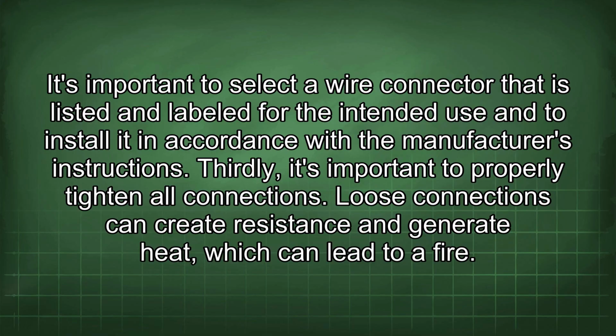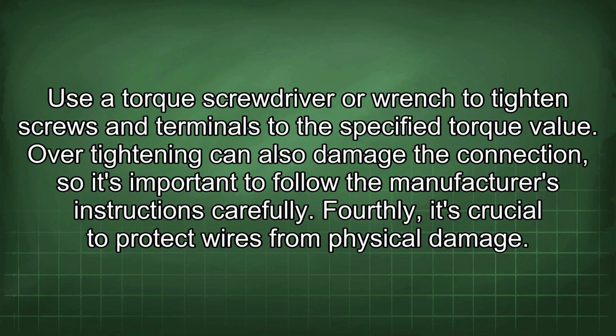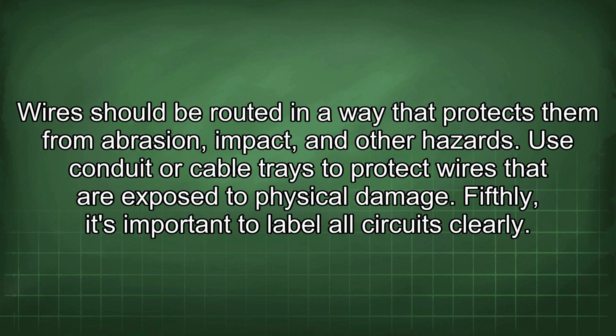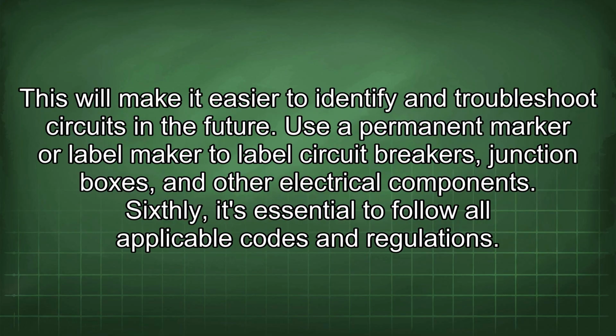Thirdly, it's important to properly tighten all connections. Loose connections can create resistance and generate heat, which can lead to a fire. Use a torque screwdriver or wrench to tighten screws and terminals to the specified torque value. Over-tightening can also damage the connection, so it's important to follow the manufacturer's instructions carefully. Fourthly, it's crucial to protect wires from physical damage. Wires should be routed in a way that protects them from abrasion, impact, and other hazards. Use conduit or cable trays to protect wires that are exposed to physical damage. Fifthly, it's important to label all circuits clearly. This will make it easier to identify and troubleshoot circuits in the future. Use a permanent marker or label maker to label circuit breakers, junction boxes, and other electrical components.